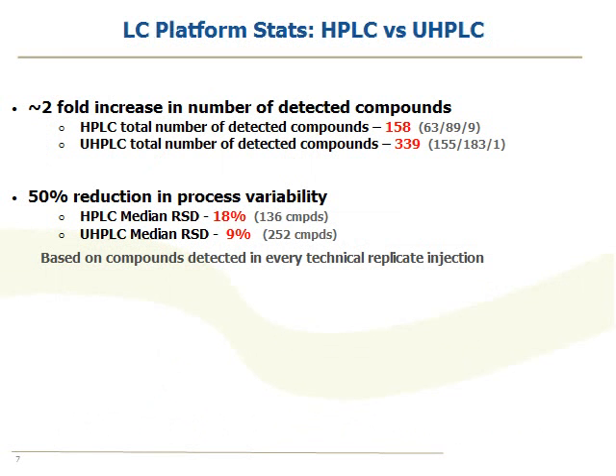The other really major improvement we were able to get out of switching to the UHPLC was a dramatic reduction in process variability. Just by making this upgrade to the LC system, we were able to decrease process variability by 50%.